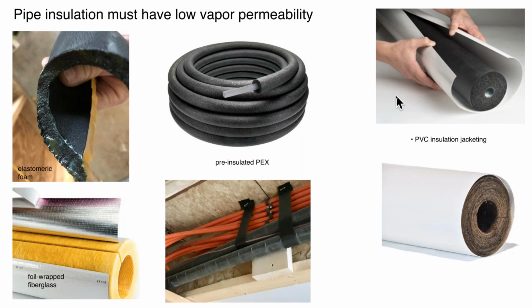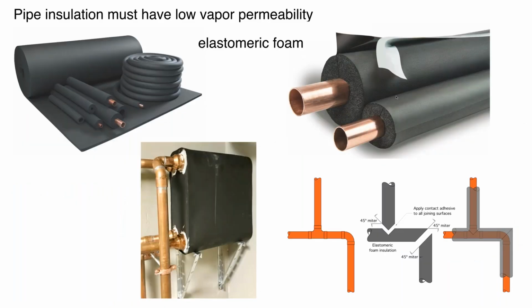Typically, when you get into commercial installations, you'll see some nicer insulation systems. They are expensive and they are labor intensive. So typically on the smaller systems, the elastomeric foam is probably the most cost effective and one of the easier products to install. You can get it in sheets, you can get it in tube lengths, or, as I say, pre-insulated tubing. It is critically important that you seal the joints up.